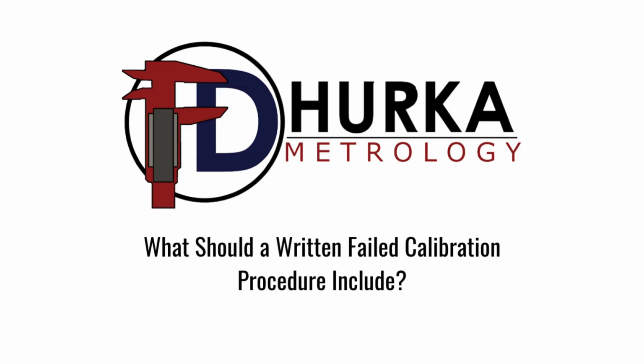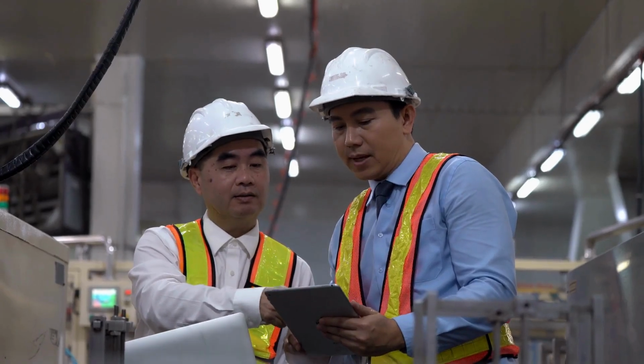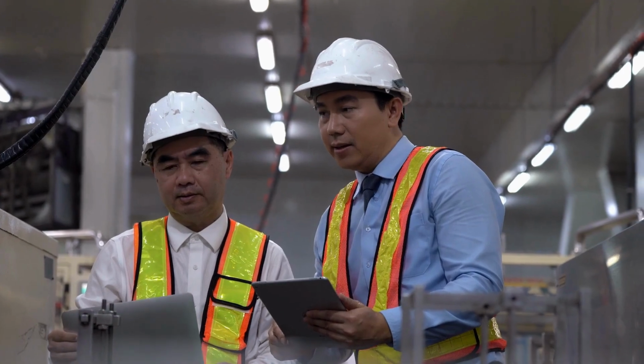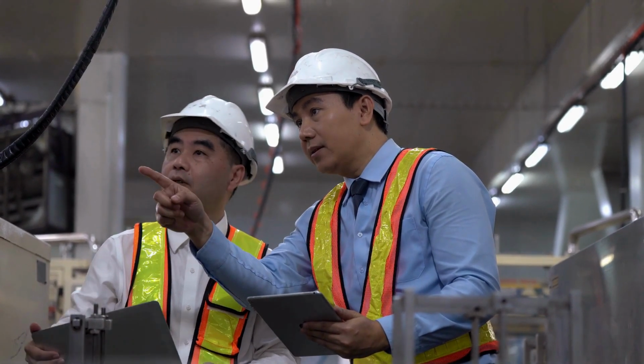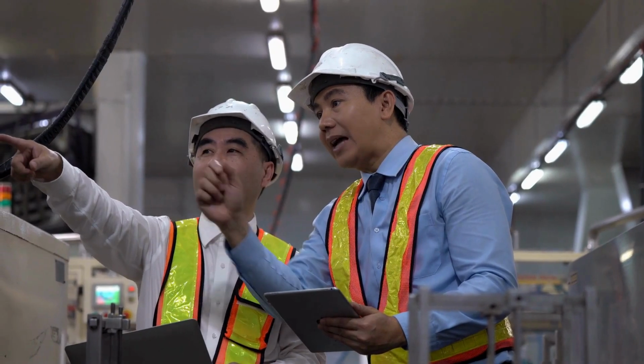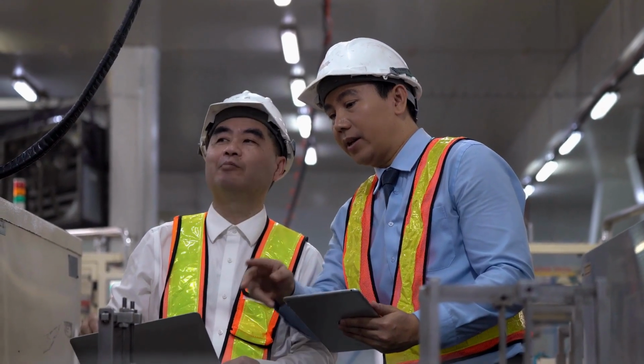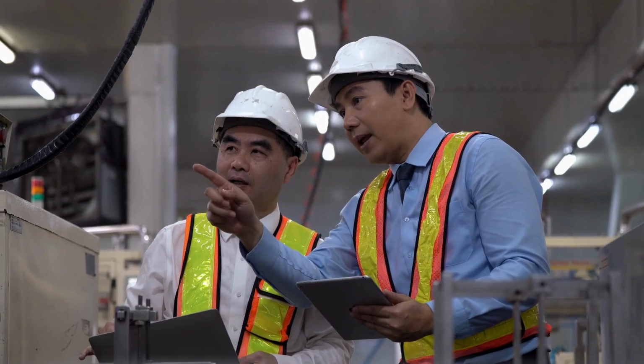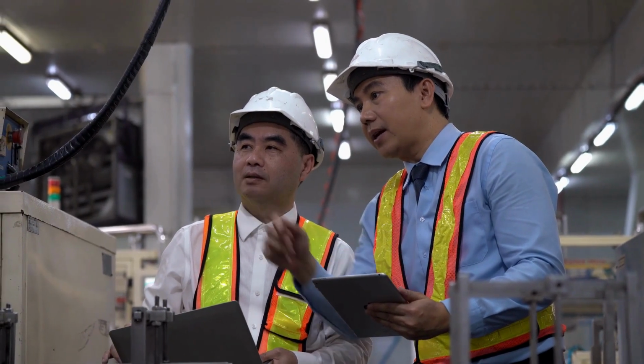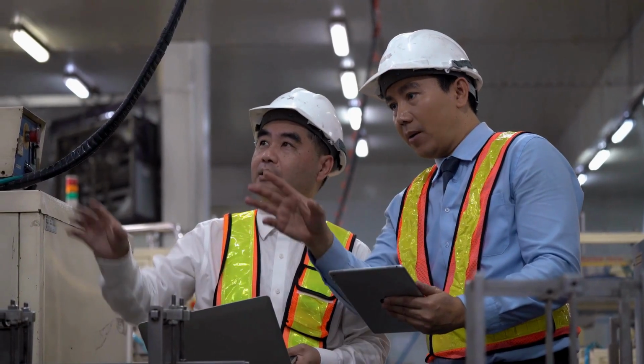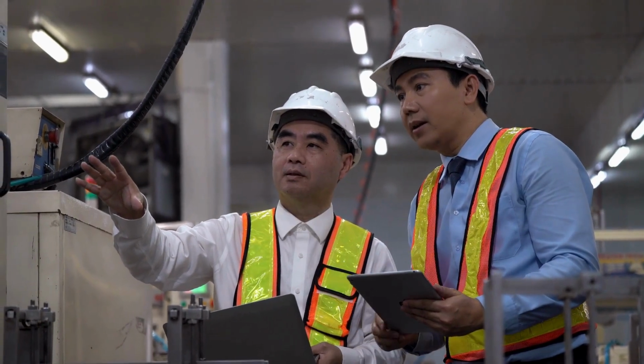What should a written failed calibration procedure include? It should define how failed tools are identified and segregated, who reviews the result, how the last known acceptable condition is determined, how prior measurements are assessed, who decides on repair or replacement, what documentation is required, and when intervals or procedures must be reviewed.